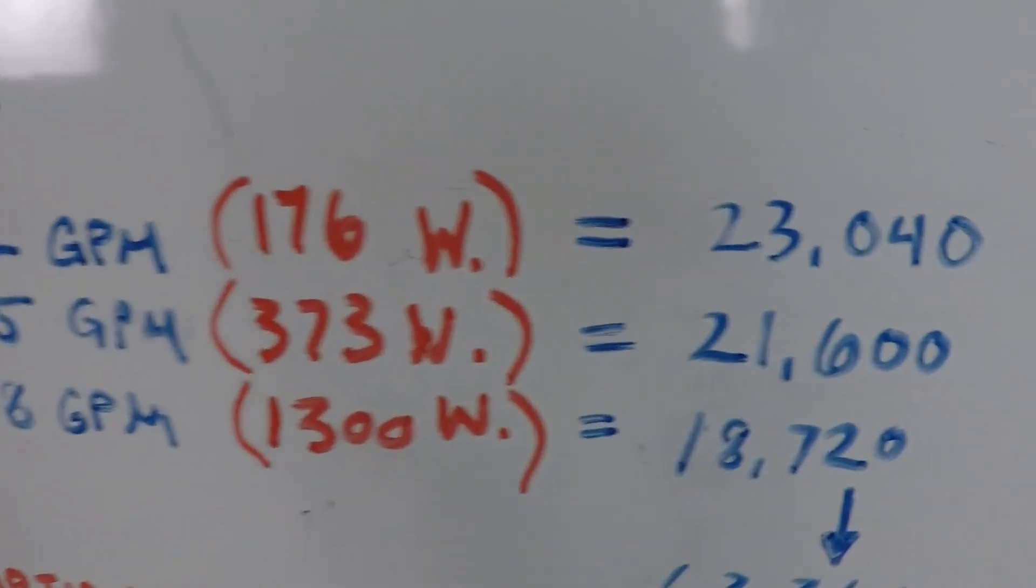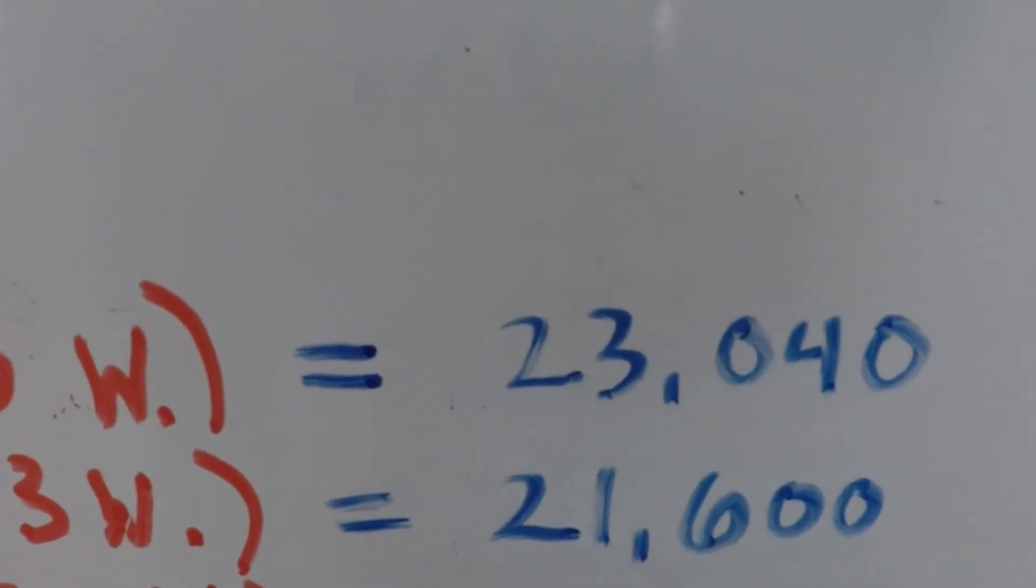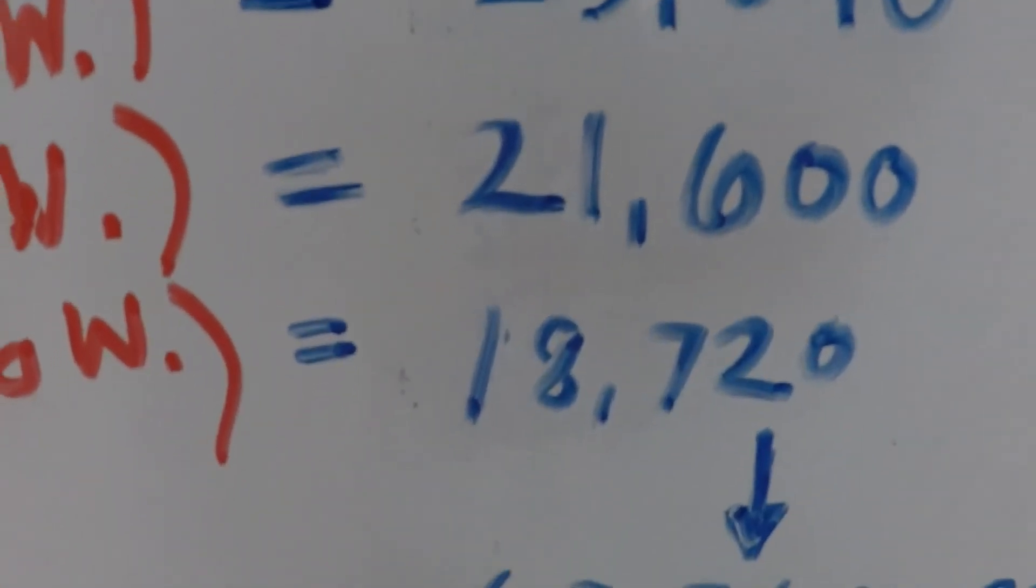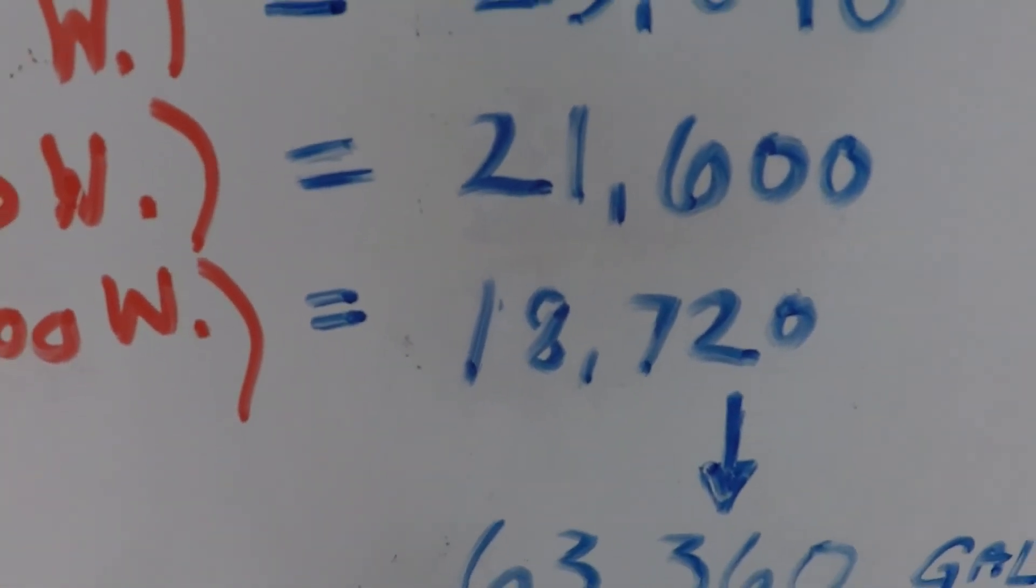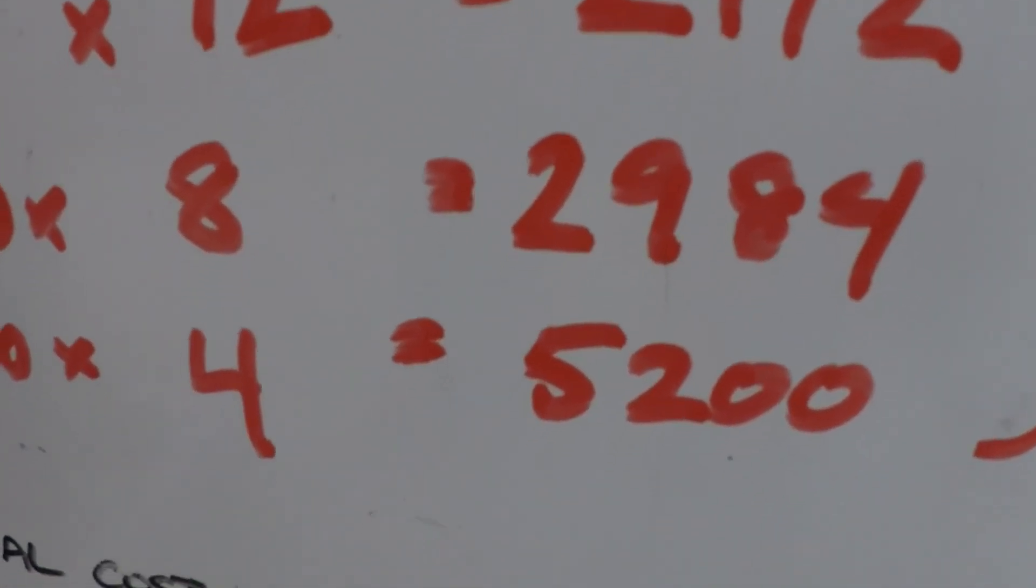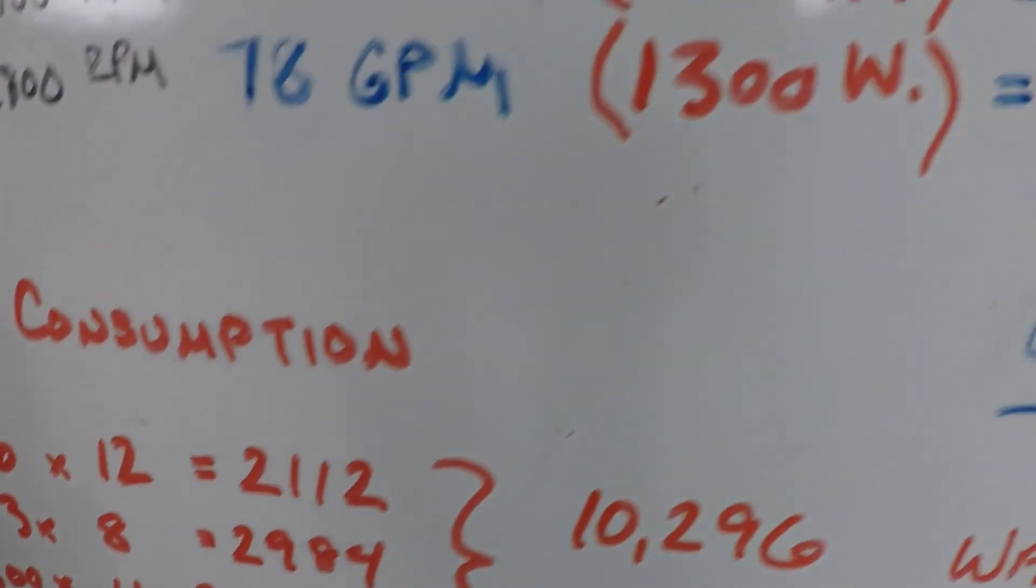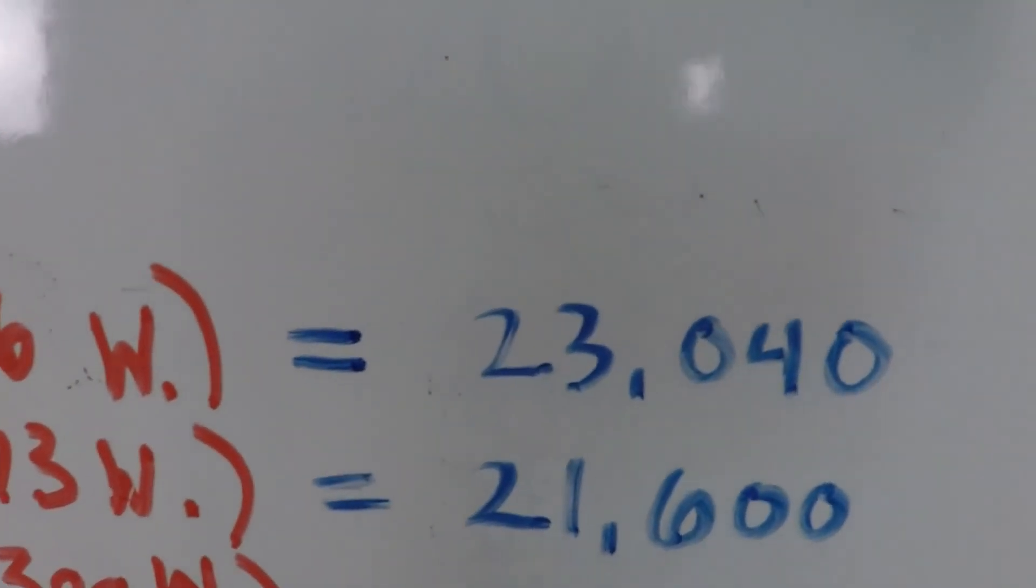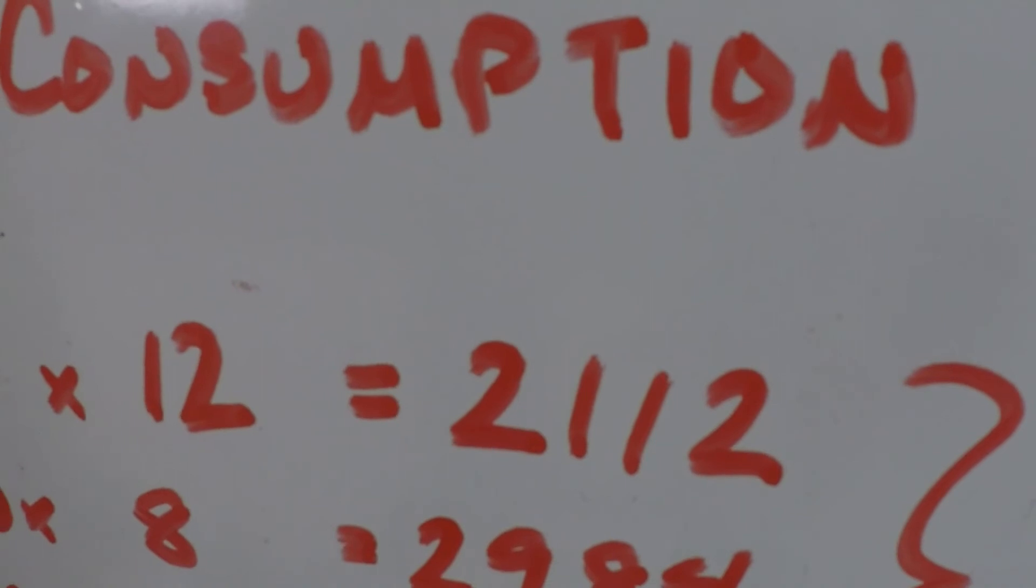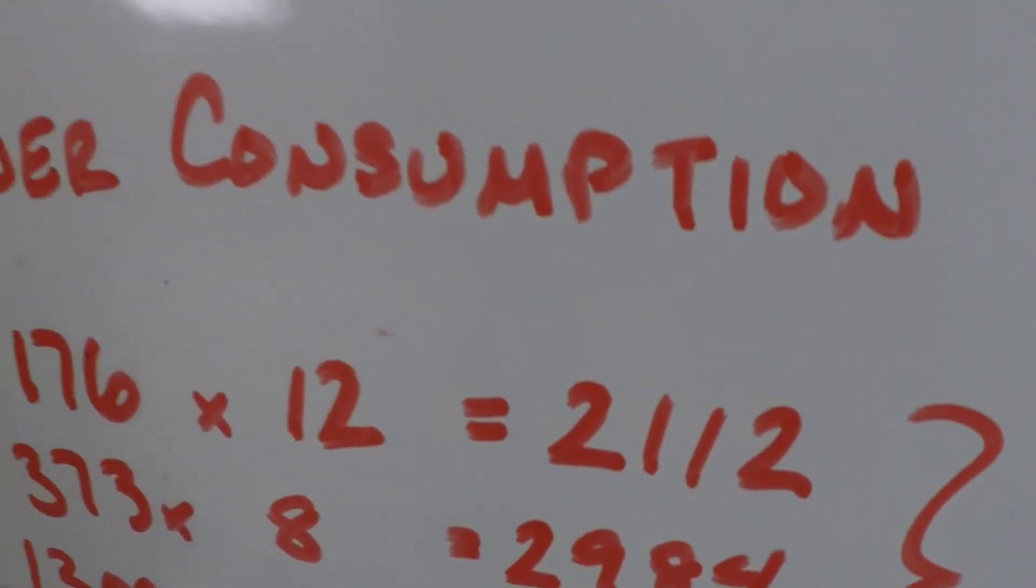Less than half the amount of power consumed over a 12 hour period versus a much higher amount of power consumed in only four hours. It's also significant because in the low speed operation we filtered 23,000 gallons of water. At high speed only 18,000. 18,000 gallons for 5200 watts of power consumption or 23,000 gallons for 2,000 watts of power consumption.